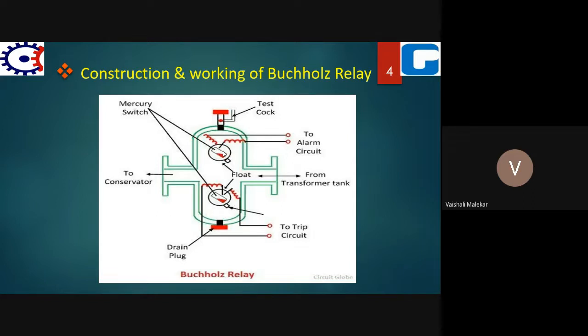And due to that, what will happen? The mercury switch closes the contacts of the alarm circuit. Now the amount of gas collected at the top side can be viewed through the window provided on the walls of the chamber. Samples of these gases can be taken and analyzed. The amount of gas indicates the severity of the fault, and its color indicates the nature of the fault.